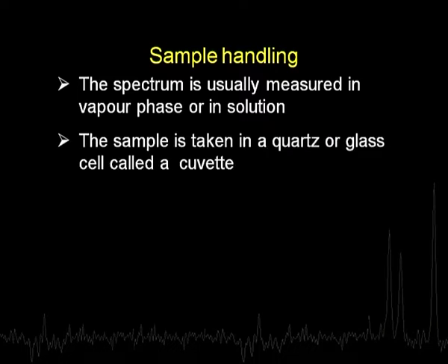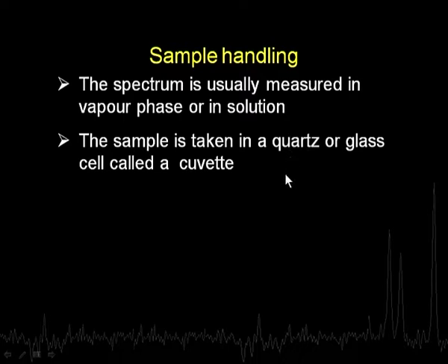Now let us see how we handle the sample. Sample handling basically means that the spectrum is typically taken either in the vapor phase or in solution, most often in solution. We need a container to hold the sample, which is typically a quartz or glass cell called a cuvette. Quartz is most often used because glass is not suitable for the UV range - glass absorbs in the UV range. Quartz is a little expensive but is more often than not the material of choice.